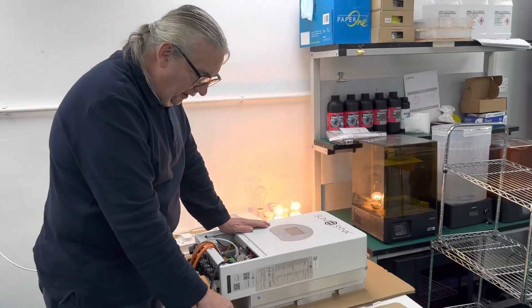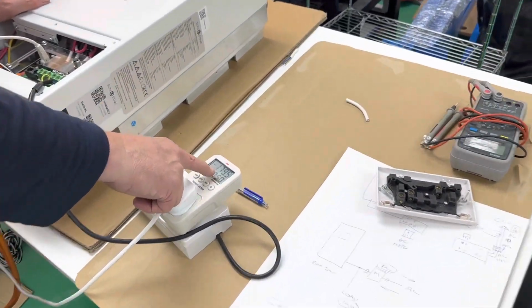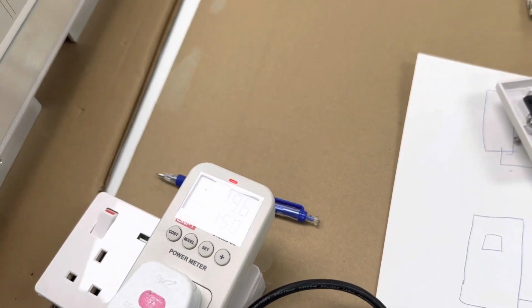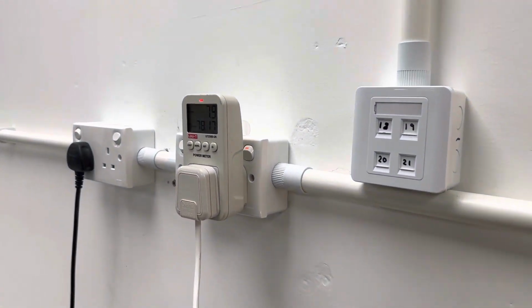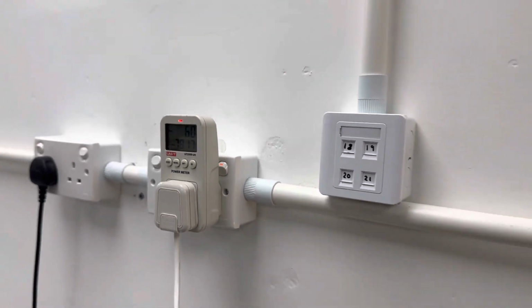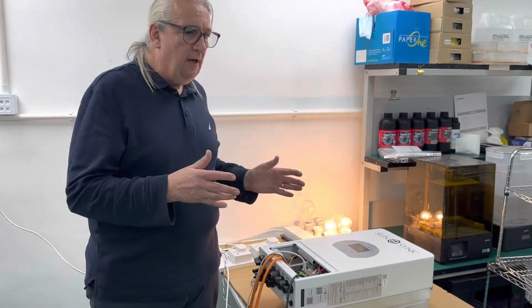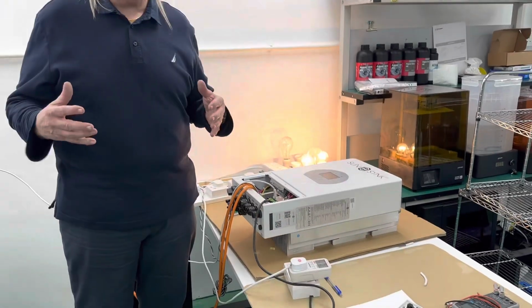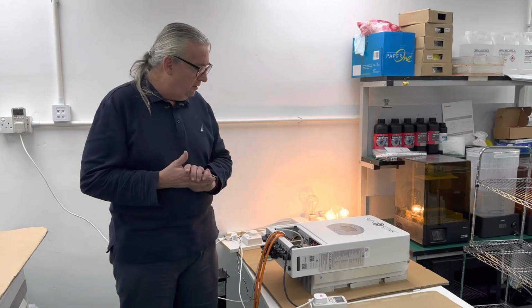Here is a meter, which is basically like your export meter. You can see the export meter here is reading 189 watts, it's exporting power. But here we've got another meter, which is my grid meter, and you can see there's very little power. It's actually importing power at the moment. So why is my inverter meter, my generation meter, showing an export, yet my other meter showing an import?